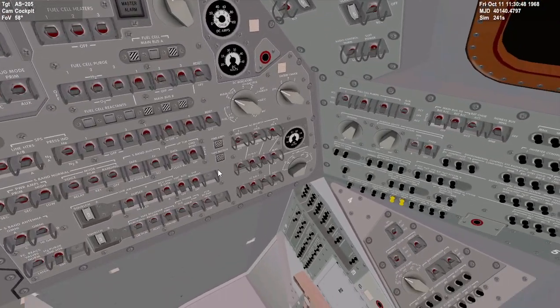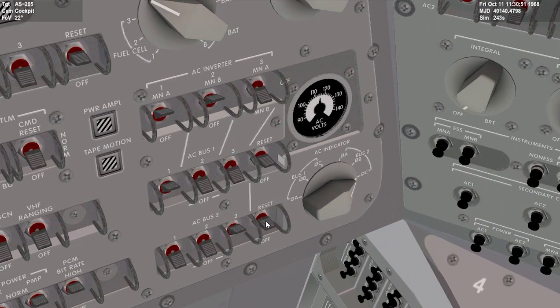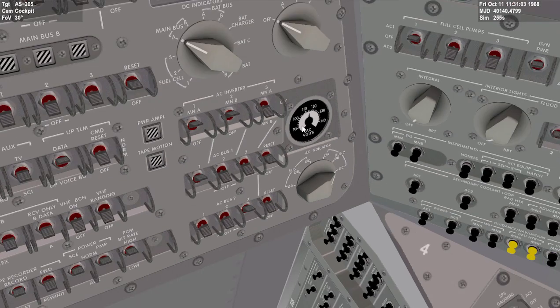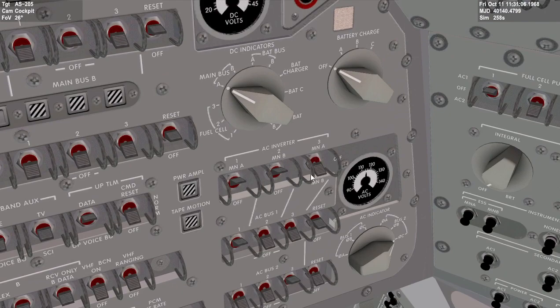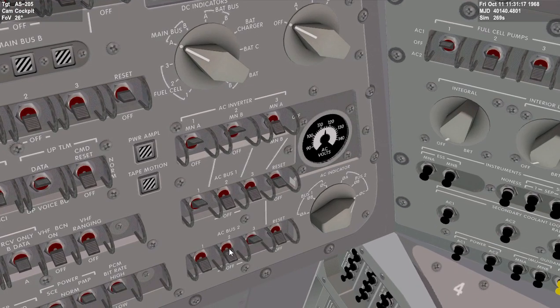Yep, so that's good. Essentially what we did there is we turned the sensors for AC2 off. We powered off inverter 2, powered on inverter 3. Well, we didn't power off inverter 2. So the power for the inverter is received by the main buses. Input, main bus A, main bus B, and 3 can go on either one. These tie it to the bus. So we just took off the tie from 2 and tied 3 to the bus and turned back on the sensor with the reset switch. And we verify we're holding AC volts. That's good. Turn the sensor off.